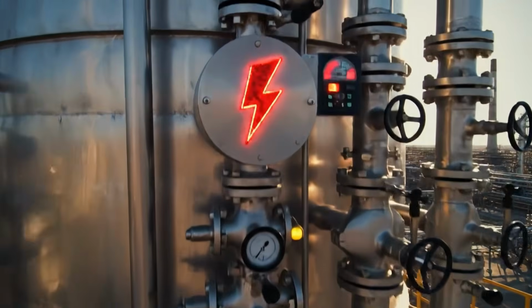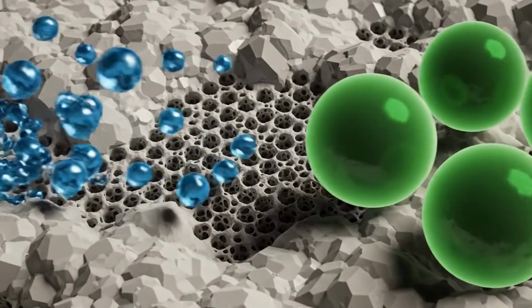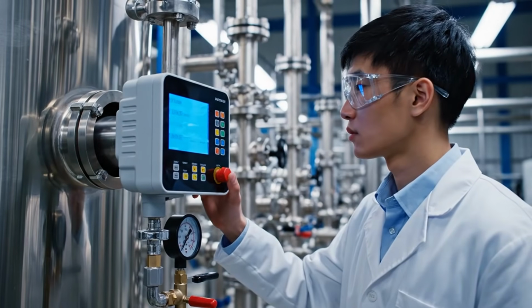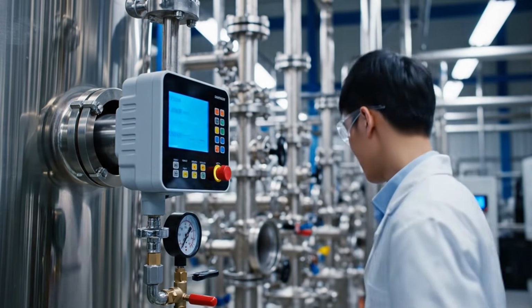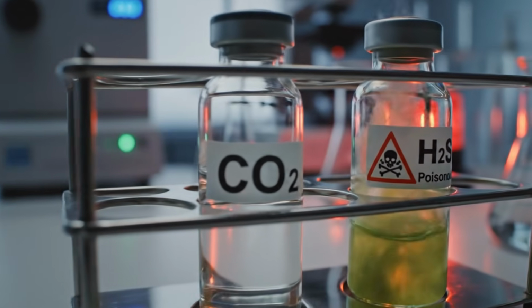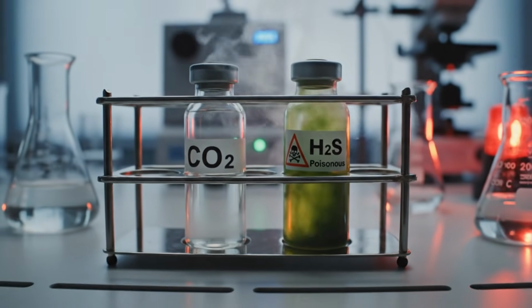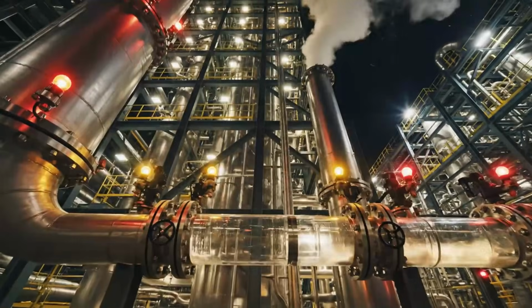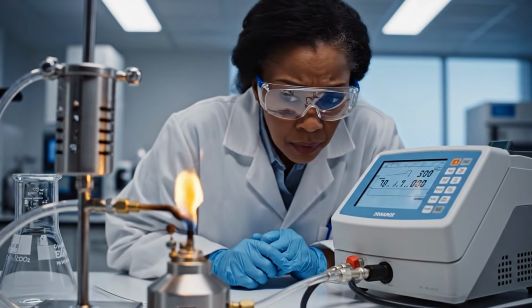Correct separation allows for the optimization of both the quality of the gas sold and the economic utilization of the reservoir. At this stage, the presence of nitrogen, mercury, and traces of other compounds is also controlled. Mercury, even if it appears in minimal amounts, can damage aluminum equipment used in certain cryogenic plants. Therefore, some facilities incorporate specific adsorbent beds to capture it before it causes operational problems. Everything is oriented toward the same end, converting an irregular and aggressive stream into a homogeneous, stable, and safe fuel.